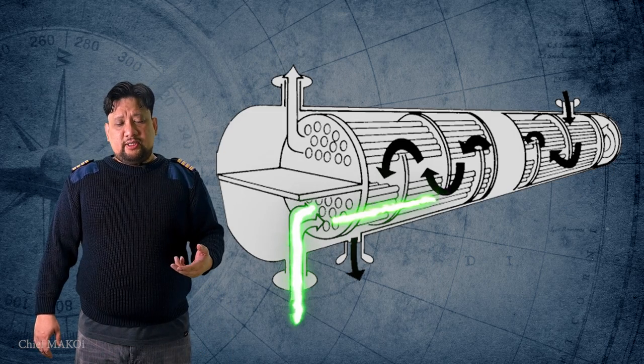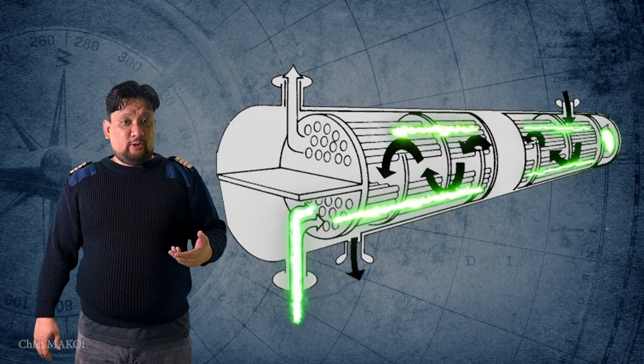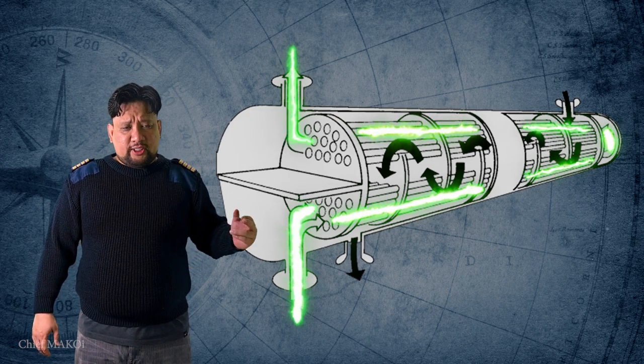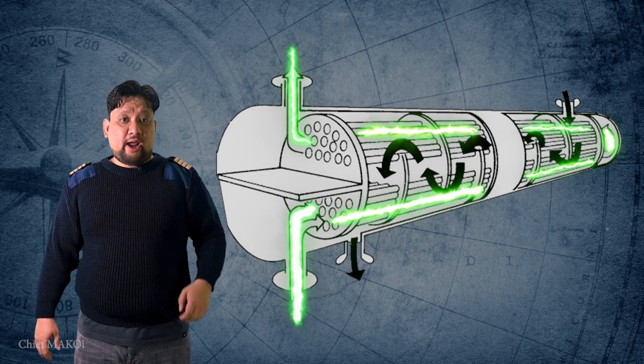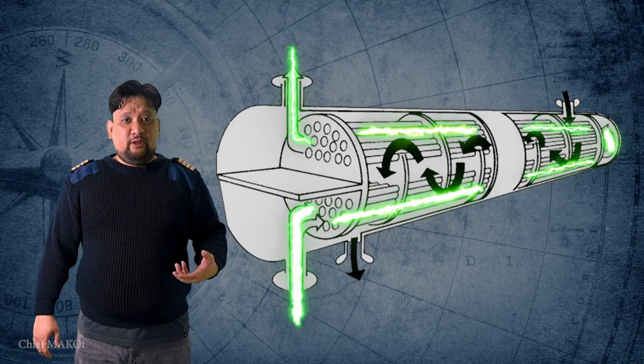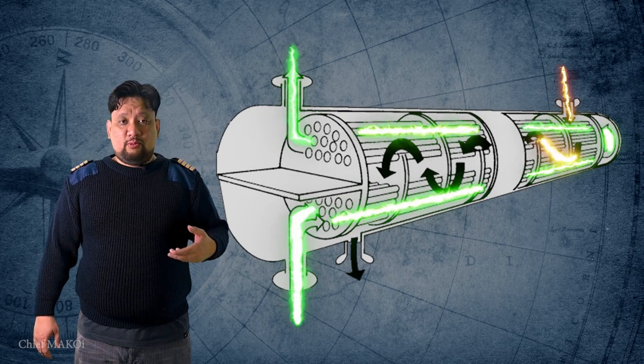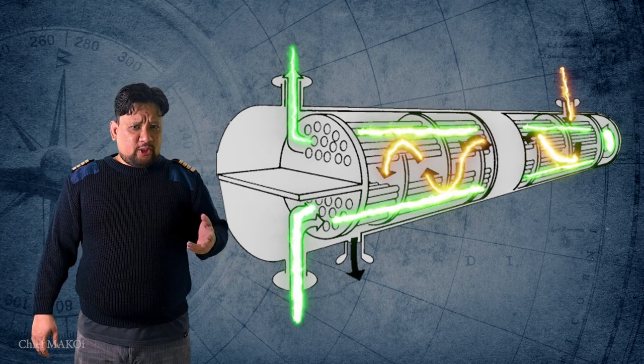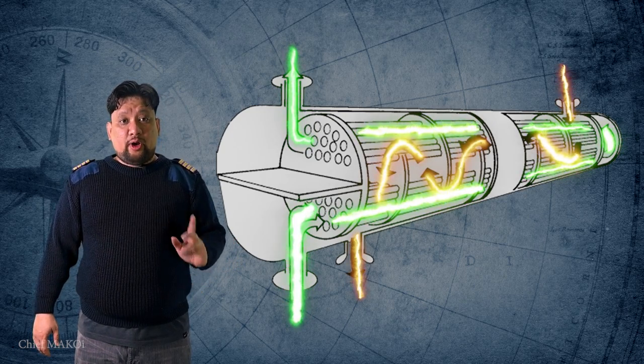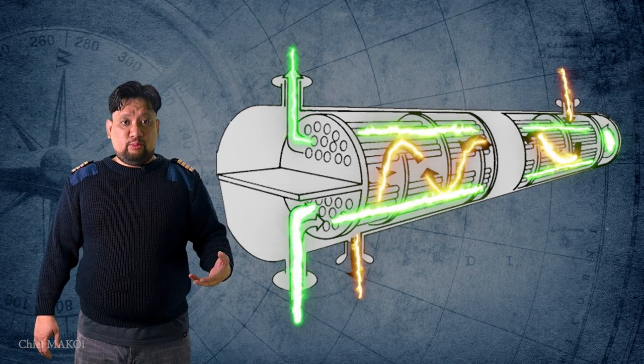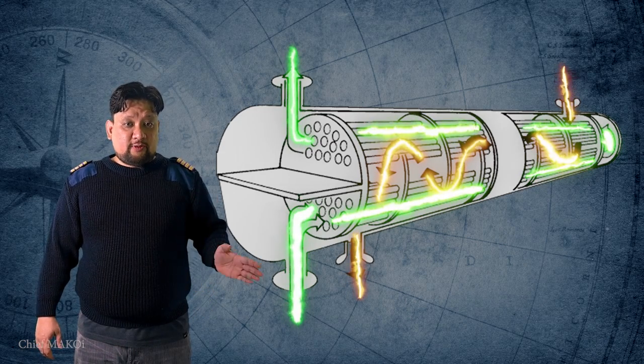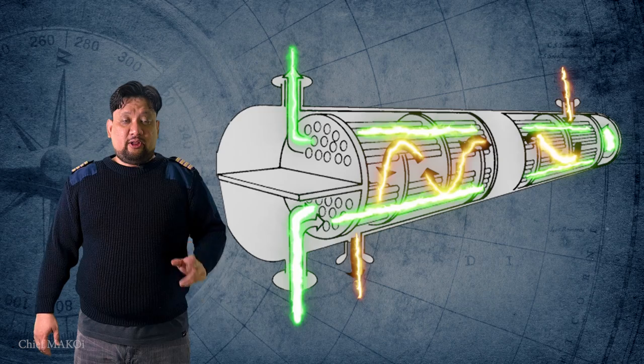In tube type coolers, the seawater being the fluid used as coolant passes through a set of tubes usually made of brass. The hotter fluid, usually jacket water or lubricating oil, enters the cooler through the shell where it comes into contact with the tubes and thereby transfers heat to the metal by conduction.